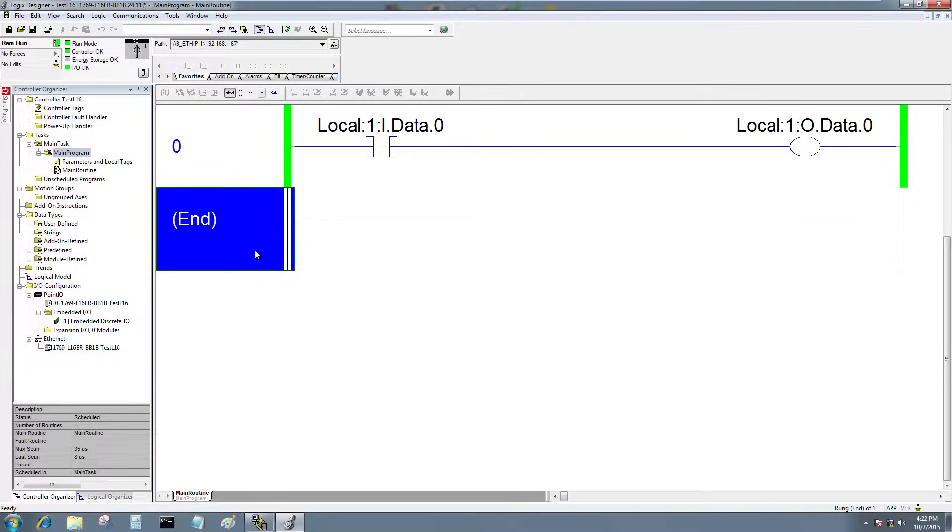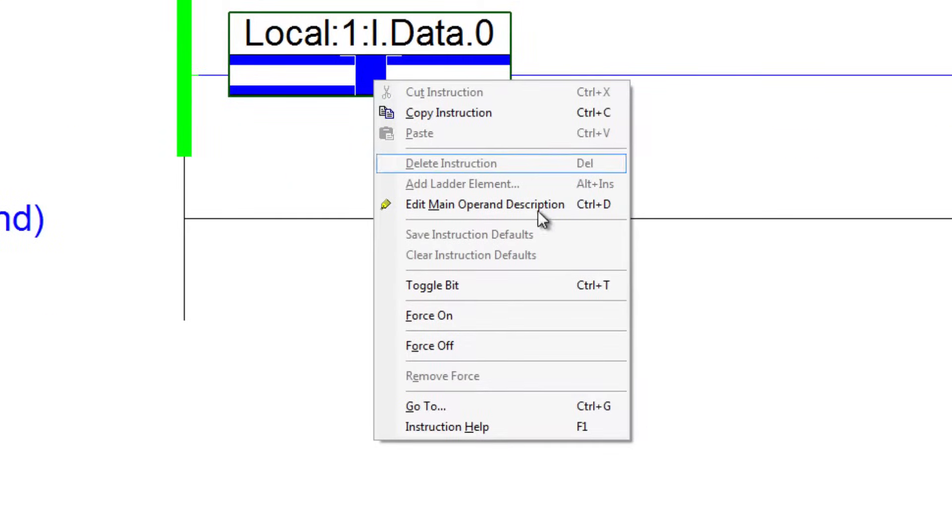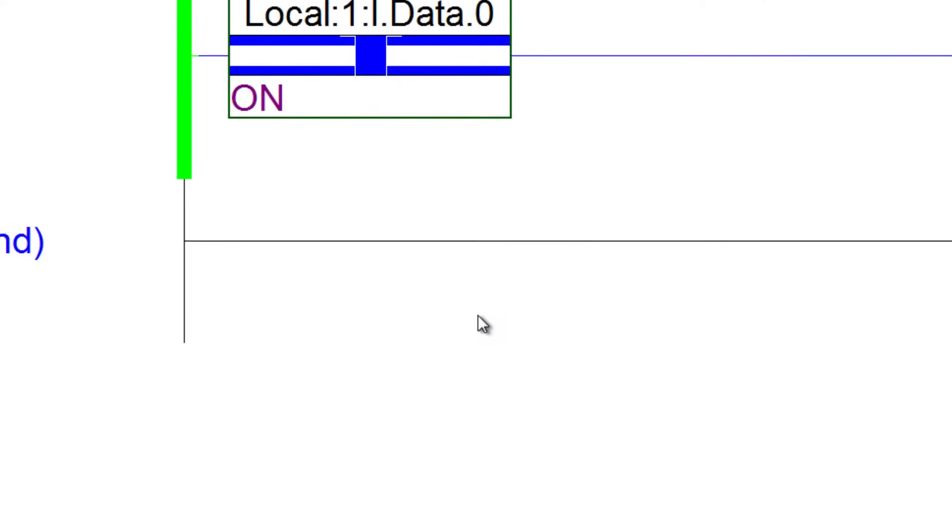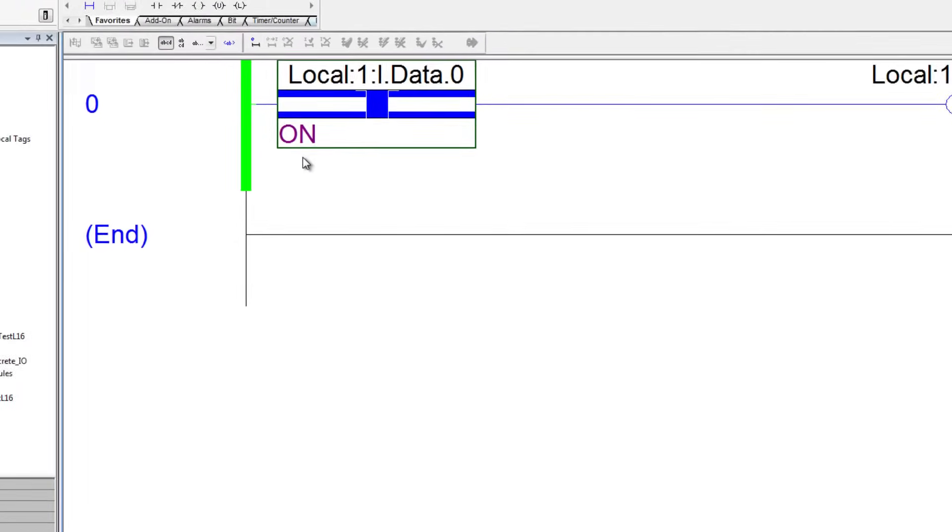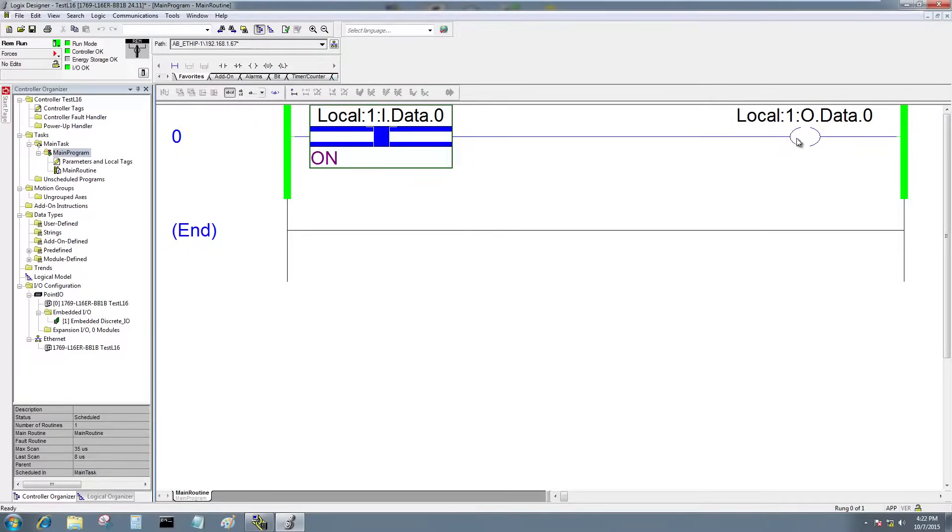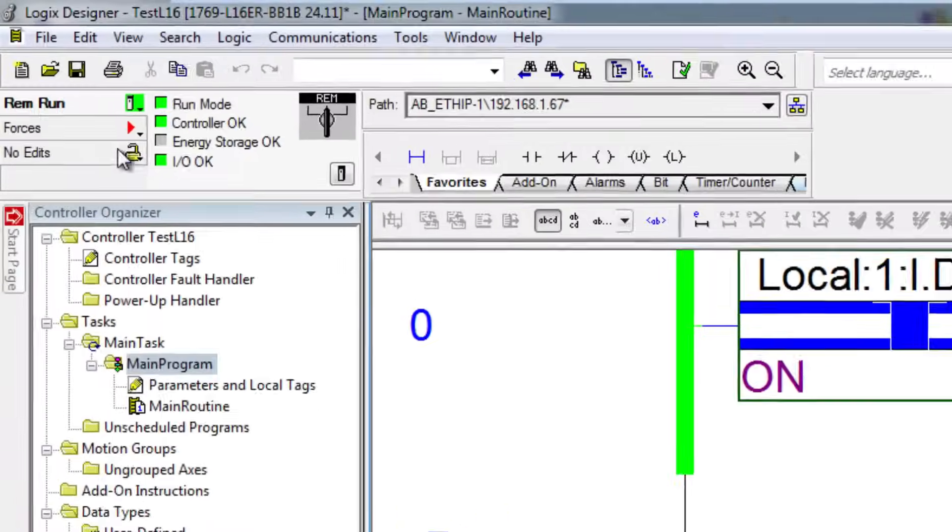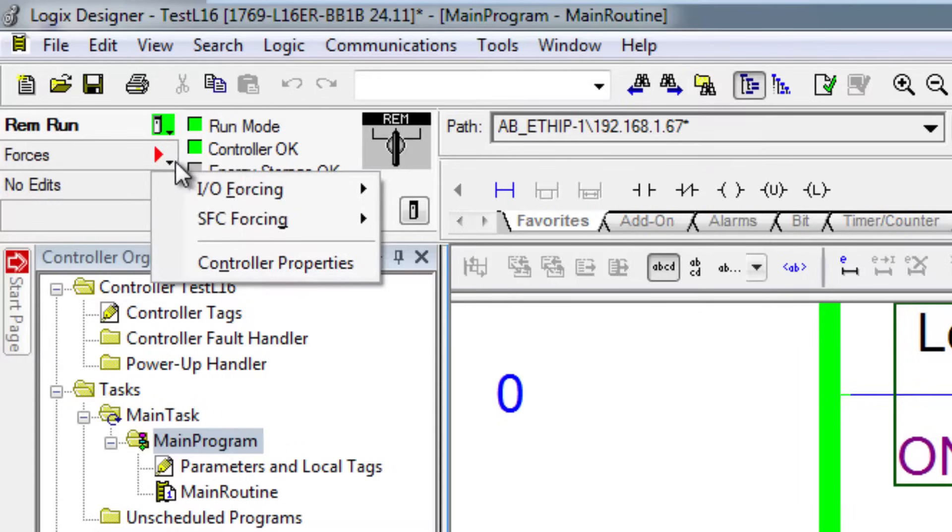I don't have anything wired to my controller yet, so I'm just going to right-click here and force this bit on. Now that force does not take effect until I actually enable forces as well.